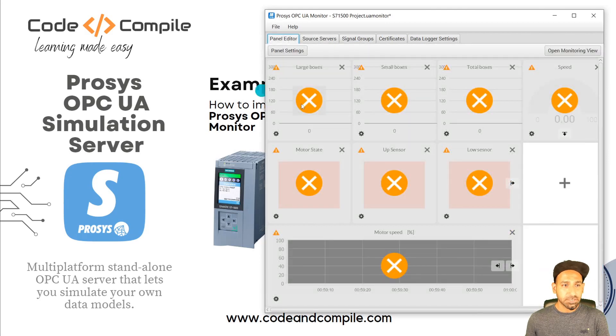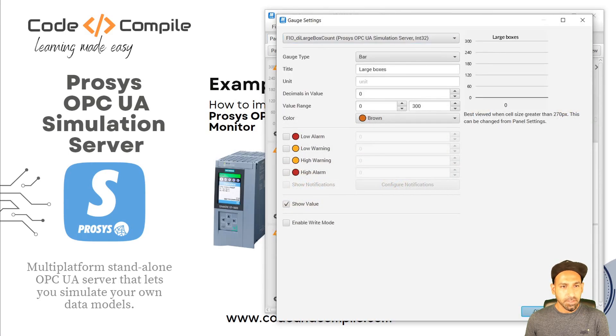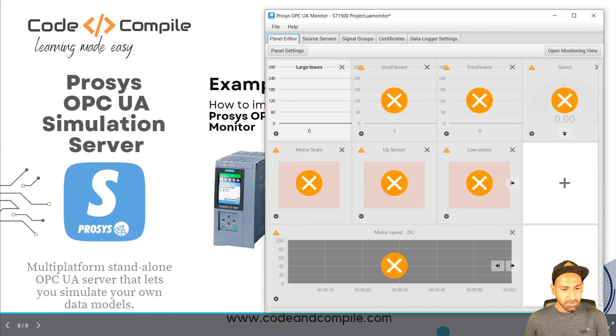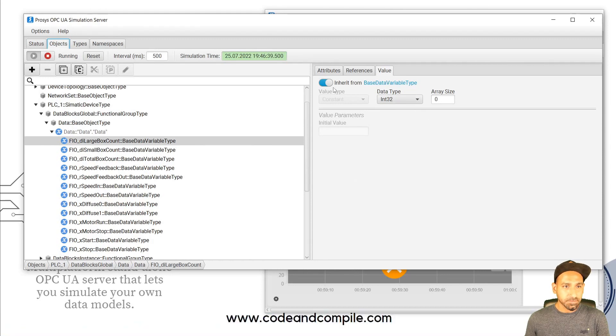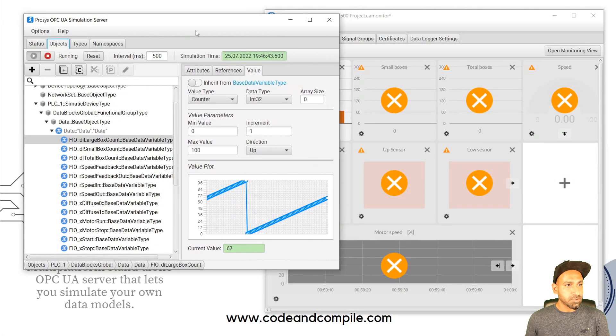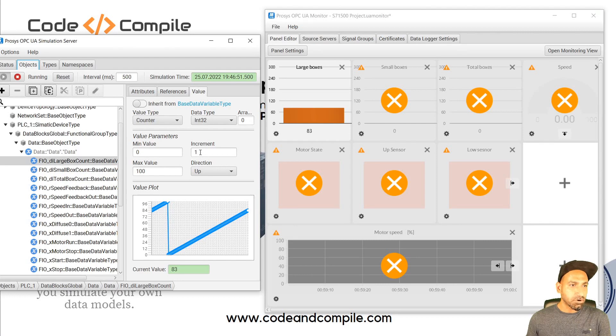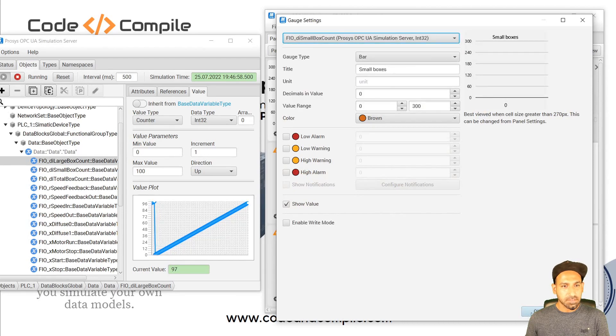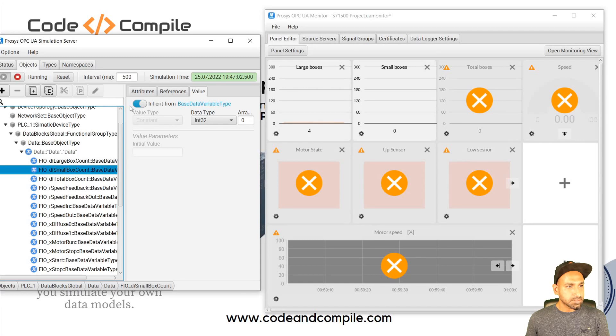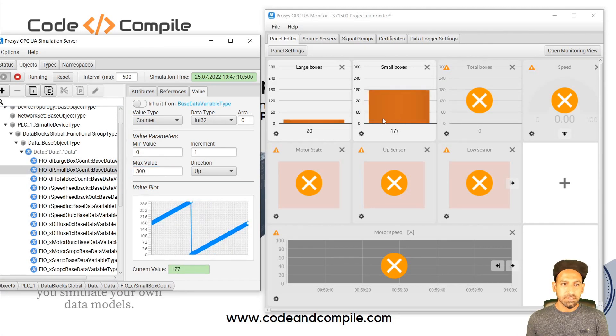In the Panel Editor, you'll see crosses because the client can't communicate to the real PLC anymore. Let's reassign the tags using the simulated variables. For Large Box Count, connect it to the simulation server tag and click OK — it now shows zero because it inherits the value by default. But you can simulate the value using the simulation functions — increment or decrement. For Small Box Count, assign it as a counter with a maximum value of 300. Do the same for Total Box Count — also set to maximum 300.